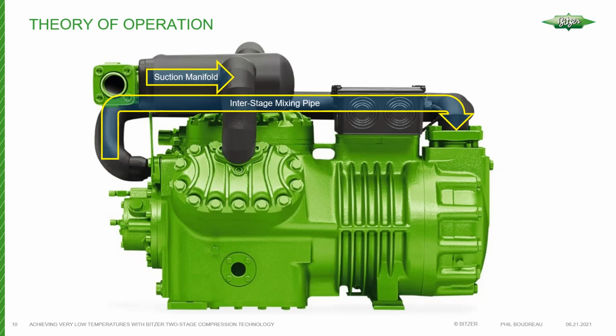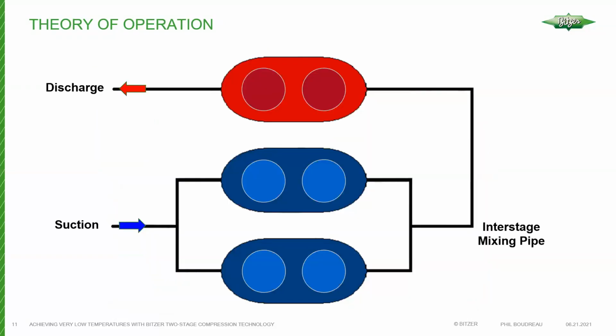So we need to have relatively cool refrigerant entering the motor. However, we just compressed it. So how cool could it possibly be? And this is where interstage cooling becomes important. We have to make sure that we have enough interstage cooling so that we don't overheat the refrigerant and the oil, but also we have enough cooling. So let's take a look at this using another approach.